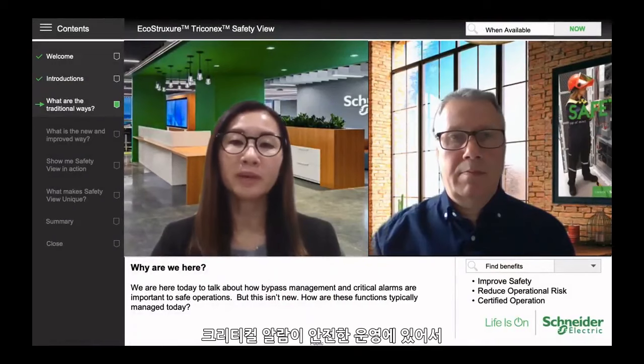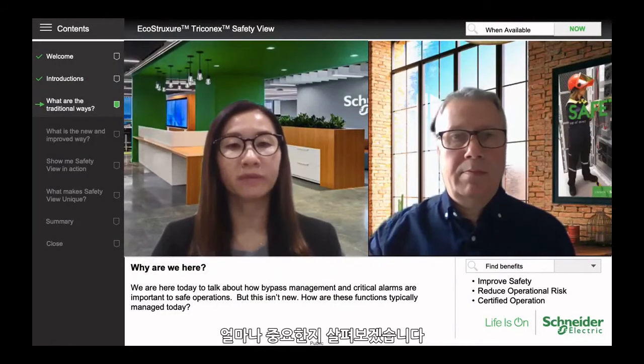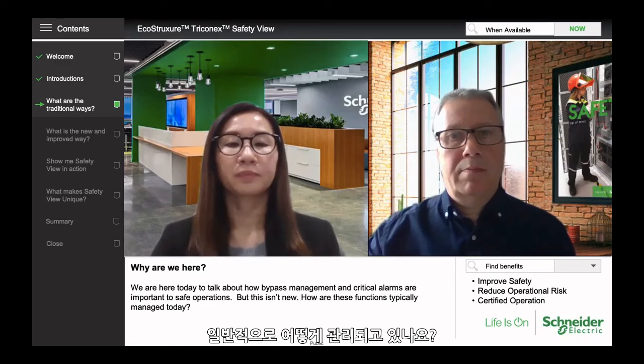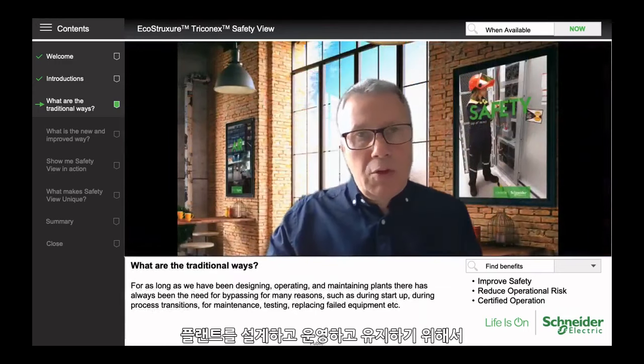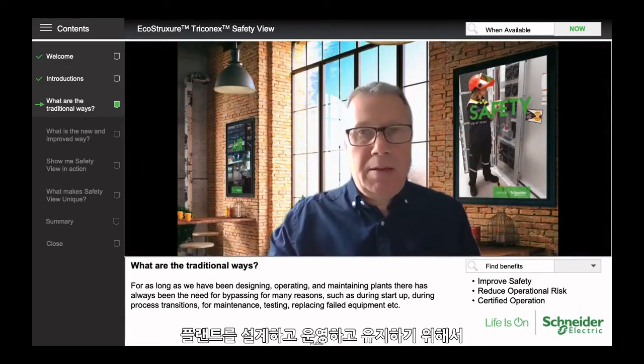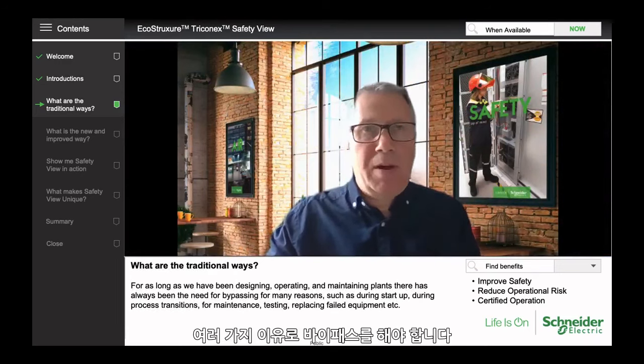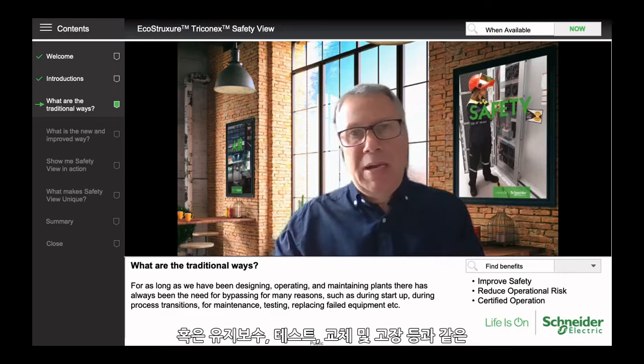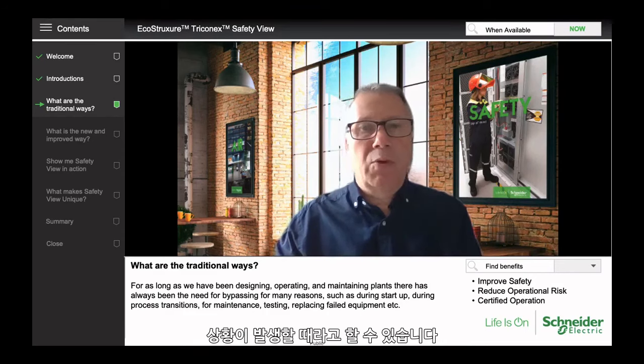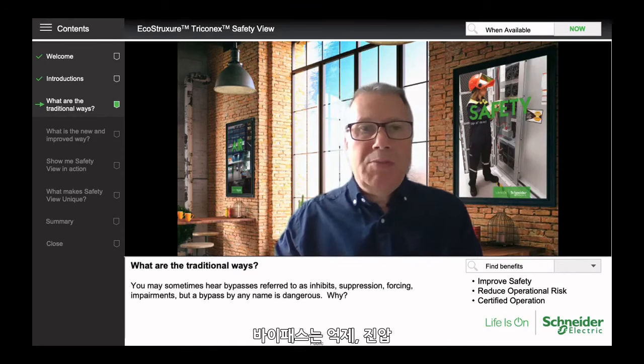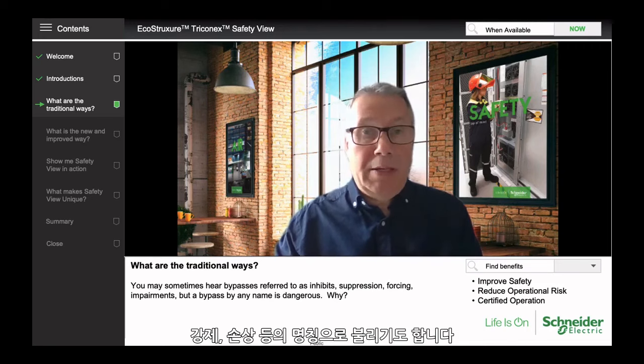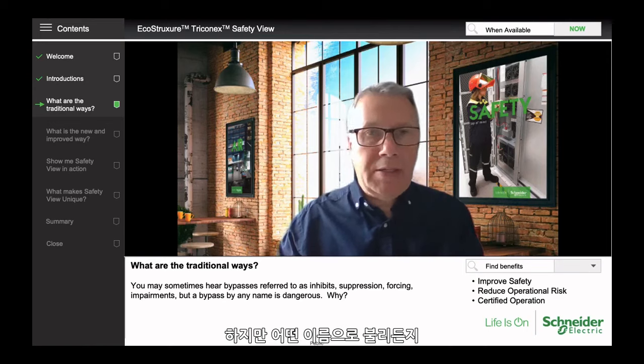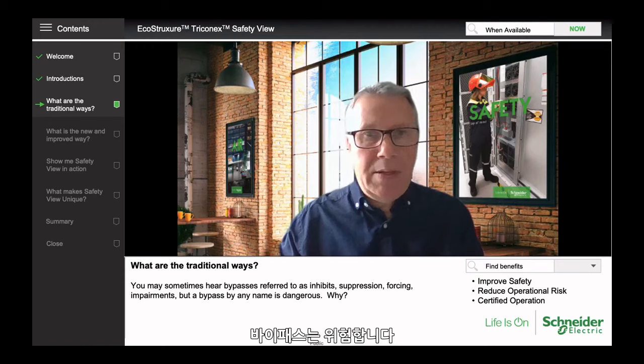We are here today to talk about how bypass management and critical alarms are important to safe operations, but this isn't new. How are these functions typically managed today? For as long as we've been designing, operating, and maintaining plants, there's always been a need for bypassing for many reasons — during startup, process transitions, maintenance, testing, replacing failed equipment, etc. You may sometimes hear bypasses referred to by other names, such as inhibits, suppression, forcing, or impairments. But whatever you call it, a bypass by any name is dangerous.